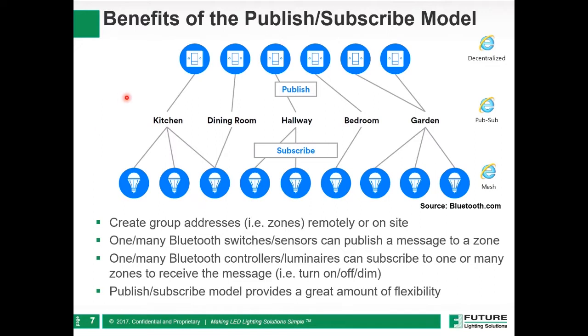With Bluetooth mesh, it's the same idea. A switch or sensor publishes a message to a group address, which we'll call zone kitchen, and the luminaires subscribe to that group address. When the switch sends a message to turn on, the luminaires receive it and turn on. You can have multiple publishers to the same group address, and a luminaire can subscribe to multiple group addresses.